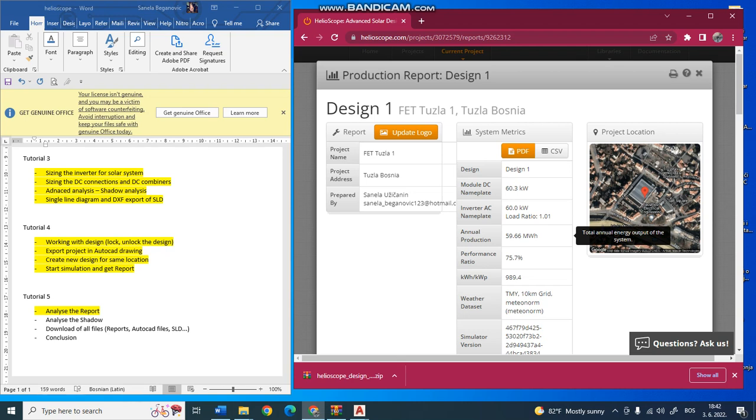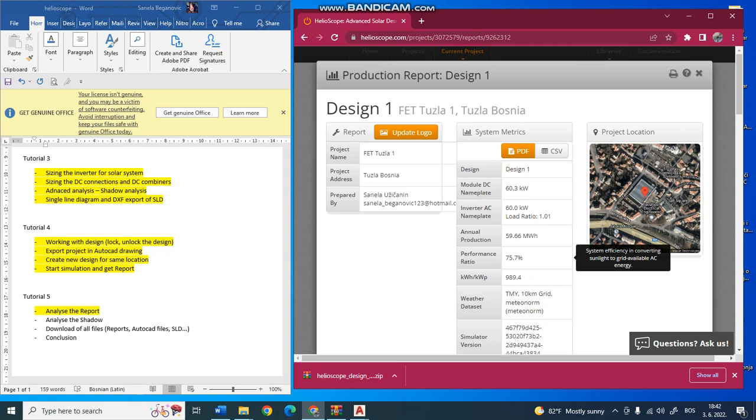Here is the annual energy production - the total annual energy output of the system per year. Next is the performance ratio, a factor going up to 100%. In a real case it cannot be 100%, of course. In this case it's 75.7%. This is the system efficiency, converting sunlight to grid-available AC energy.